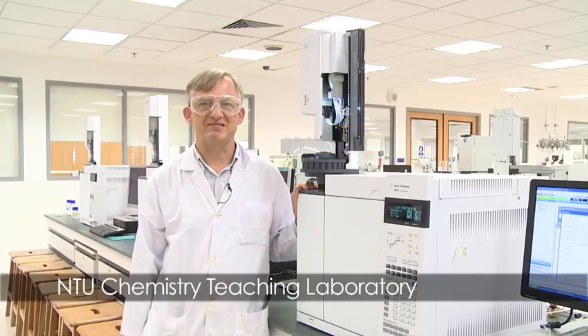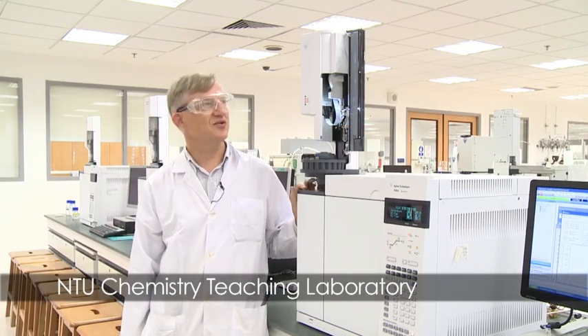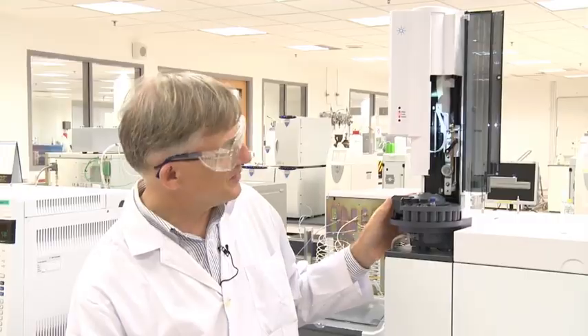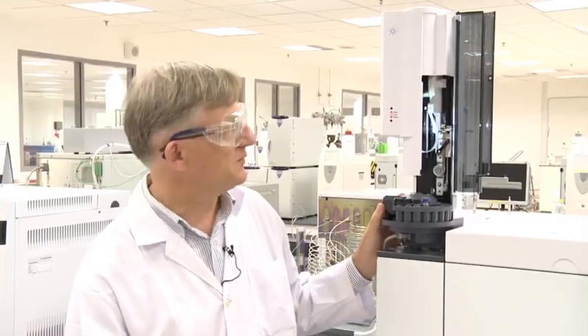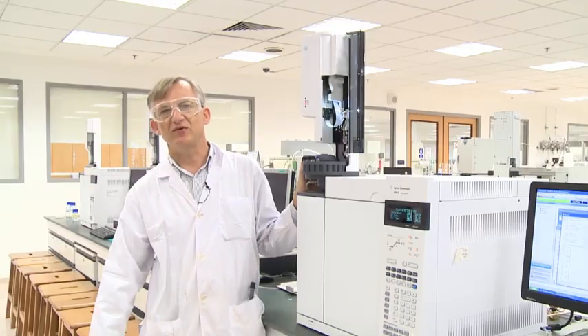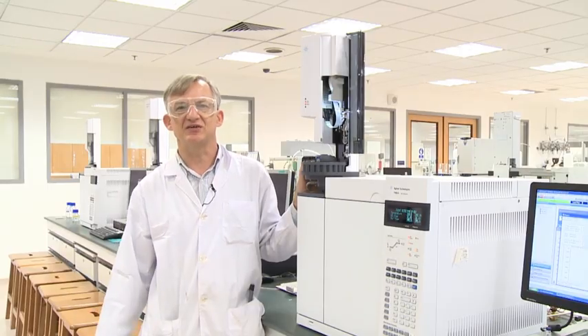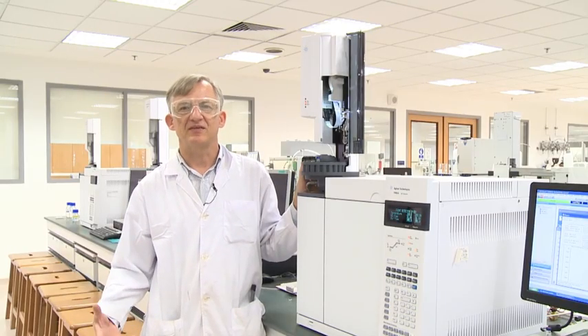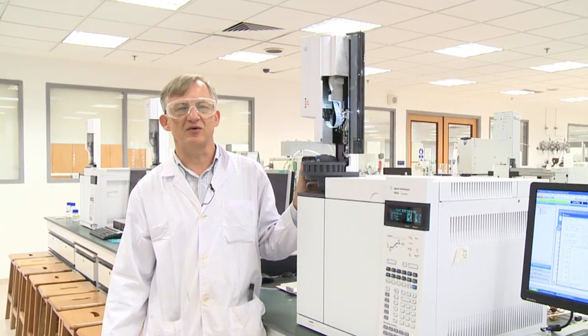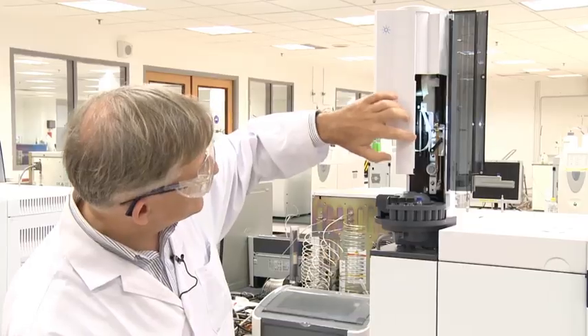This is a gas chromatograph, or GC, and this one is fitted with an auto-sampler so that it can run multiple samples one by one. The autosampler is effectively an injection robot. The sample is injected into the instrument automatically by this syringe here.